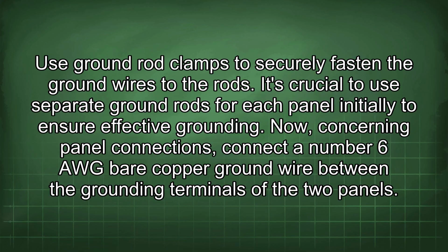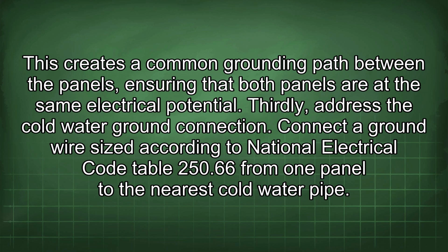Now, concerning panel connections, connect a number 6 AWG bare copper ground wire between the grounding terminals of the two panels. This creates a common grounding path between the panels, ensuring that both panels are at the same electrical potential.